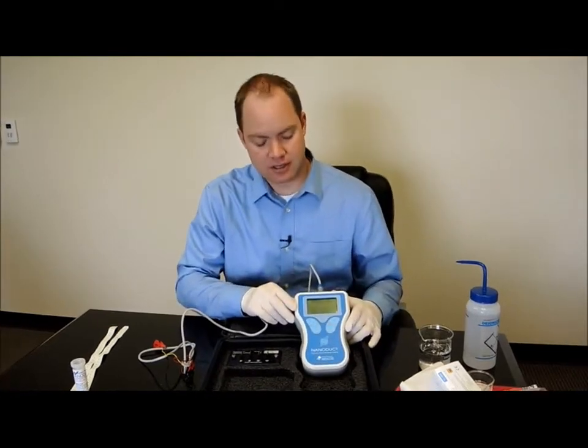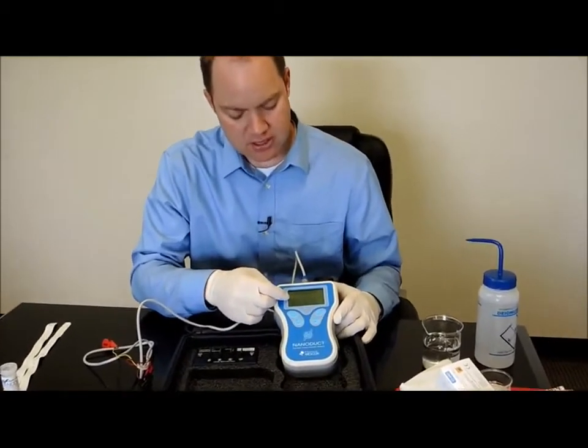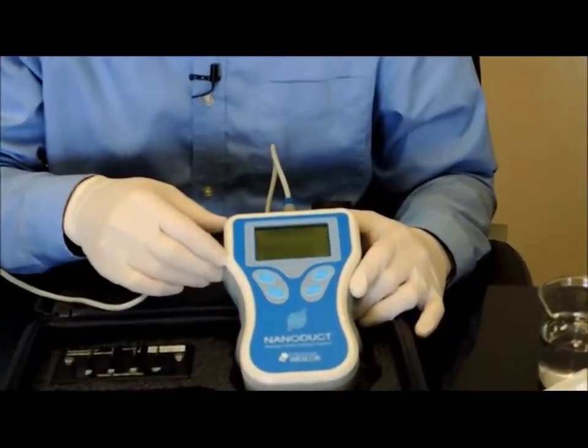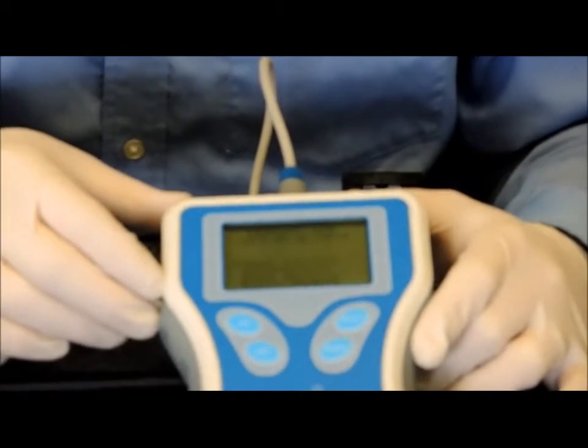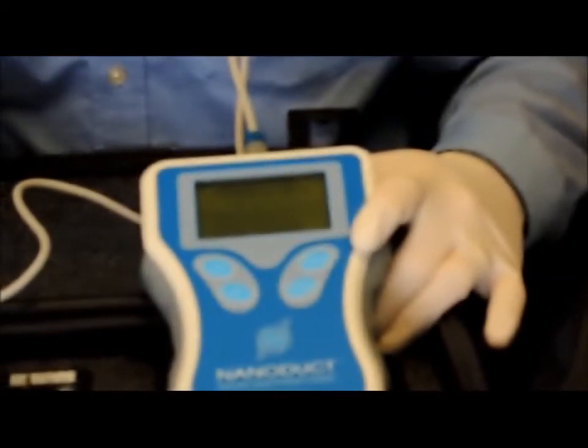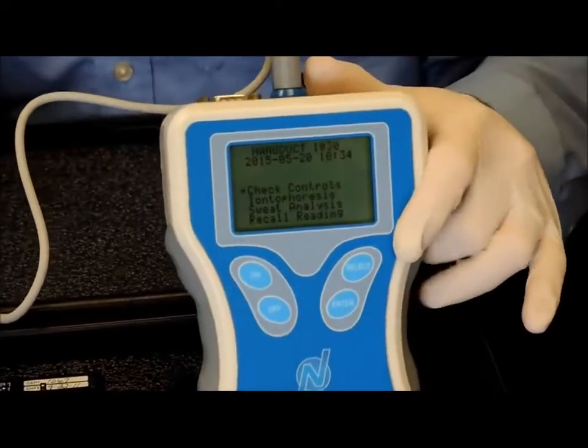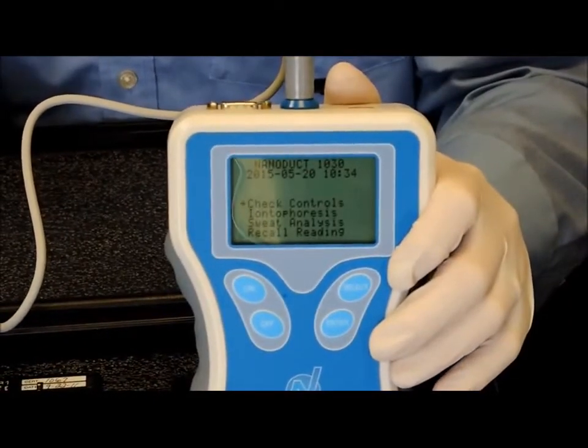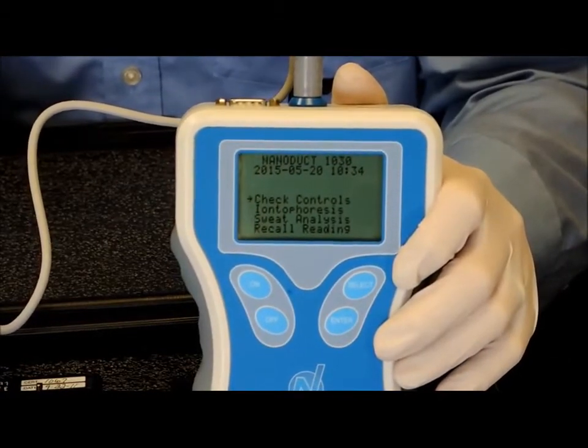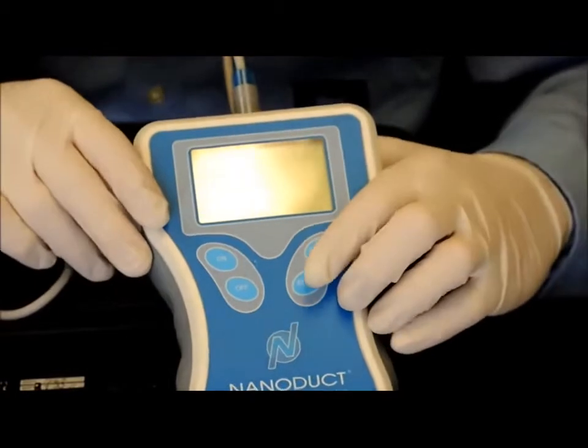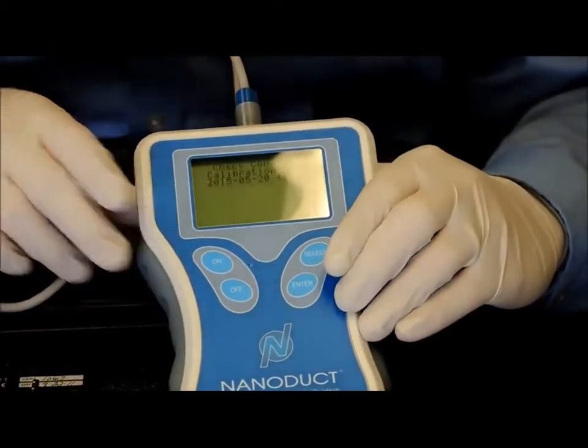With the cable connected and the Nanoduct turned on, you'll see an arrow pointed towards check controls. You also see the date and time listed on the top part of the screen. The check control should be run every day. That's used by plugging in the electrode cable, the sensor cell portion of the electrode cable, onto the calibration plate. And you should only do electronic calibration and never do liquid calibration. So I'll press enter to go into the check controls portion.